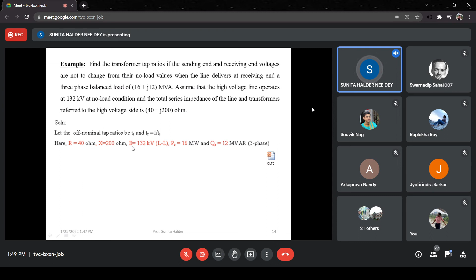Here it should be noted that phi is greater than 0 for lagging power factor, if you can remember the derivation of the short transmission line, the derivation of voltage regulation, and phi is less than 0 for the leading power factor, because accordingly you have to put that. And Ts is greater than 1 and Tr is less than 1 for the voltage drop compensation. So in that way we can find out what will be the tap setting of the OLTC both at sending end and receiving end side if we want to maintain the same voltage as at the no load condition.